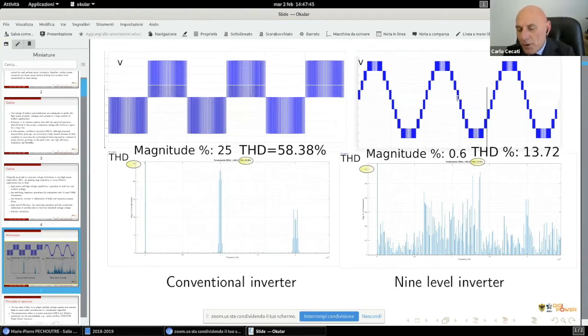But as I will show you at the end of this presentation, we are capable, and it is very convenient, to generate waveforms at fundamental frequency. So instead of having a PWM embedded within the multi-level waveform, we have just a simple staircase waveform. If we consider these two curves, with conventional PWM we have almost 60% total harmonic distortion, while with this not very sophisticated 9-level inverter, without using filters, we have 13% total harmonic distortion.